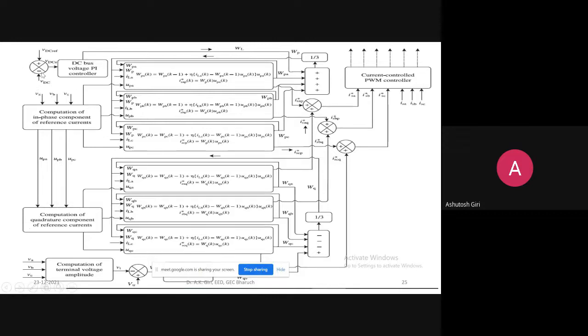That means you have to maintain at least that value for proper operation of the device. Otherwise there will not be any effective control, voltage control, frequency control, or power balancing. Nothing will be obtained if your DC goes below 700 volt. That's why a DC reference is needed, and the actual DC has to be sensed and compared.